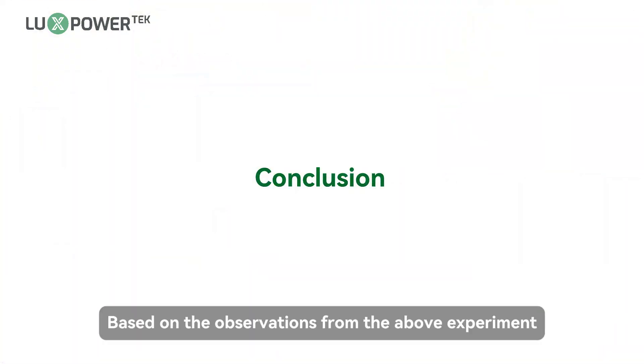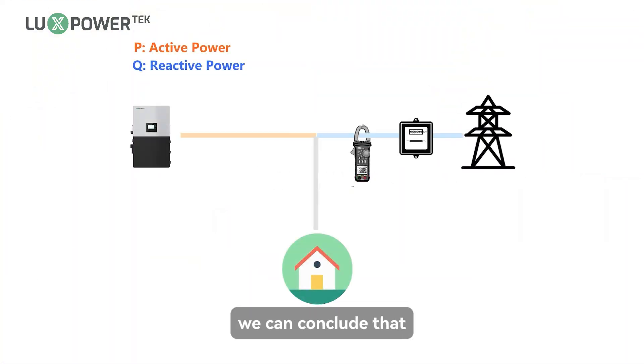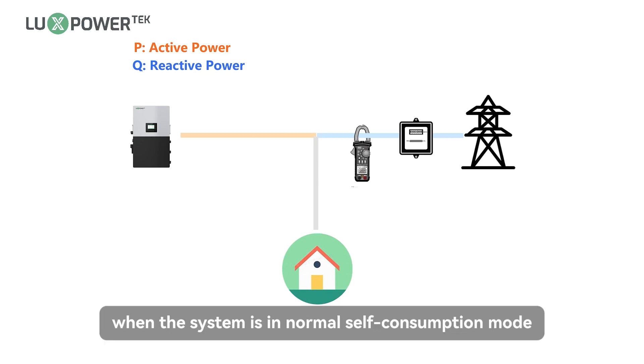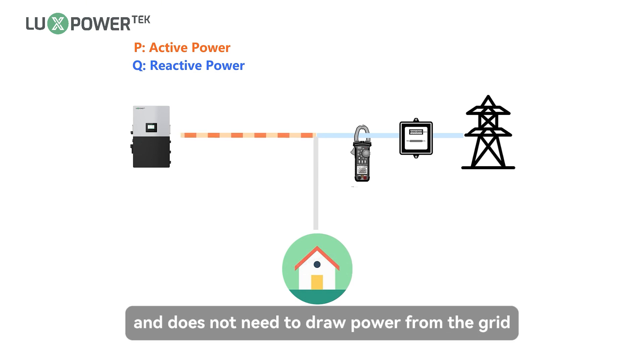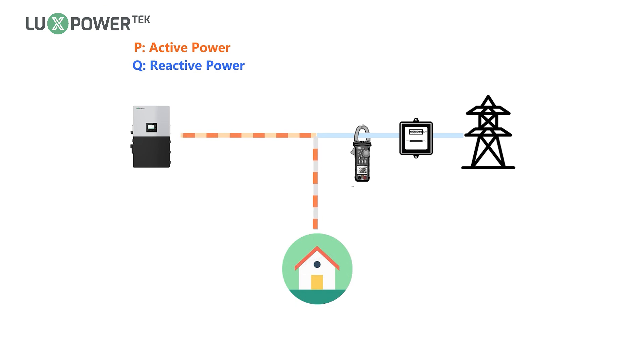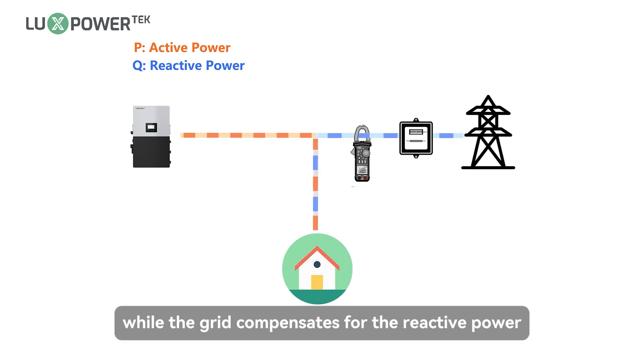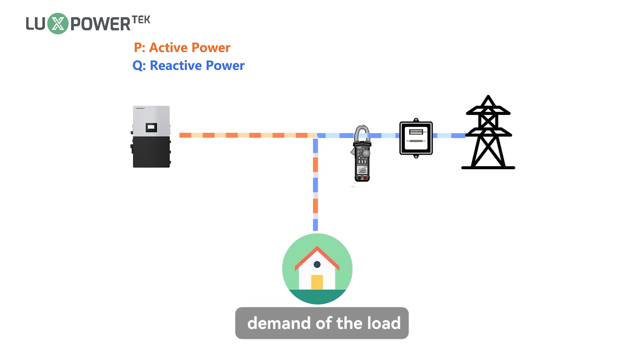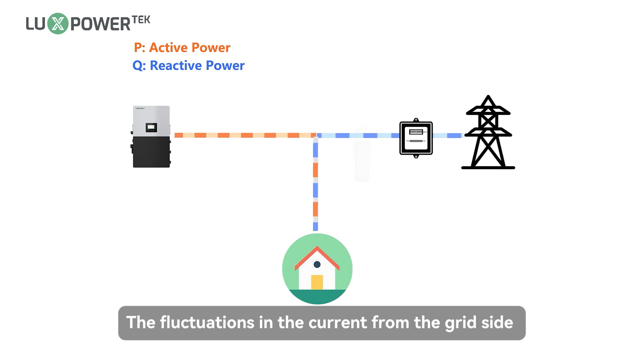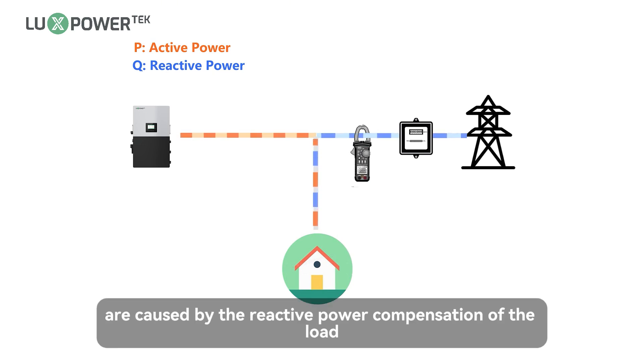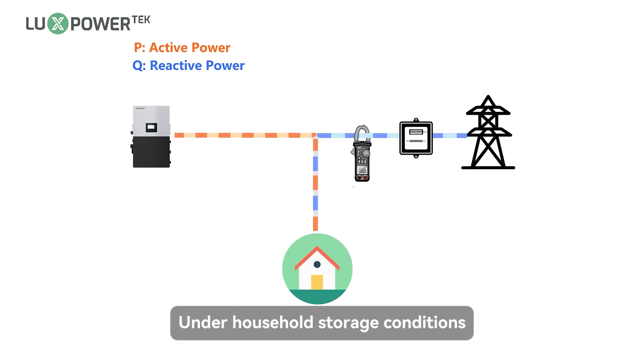Based on the observations from the above experiment, we can conclude that when the system is in normal self-consumption mode and does not need to draw power from the grid, the inverter system meets the active power demand of the load, while the grid compensates for the reactive power demand of the load. The fluctuations in the current from the grid side are caused by the reactive power compensation of the load. Under household storage conditions, reactive power is typically not included in the cost of power loss.